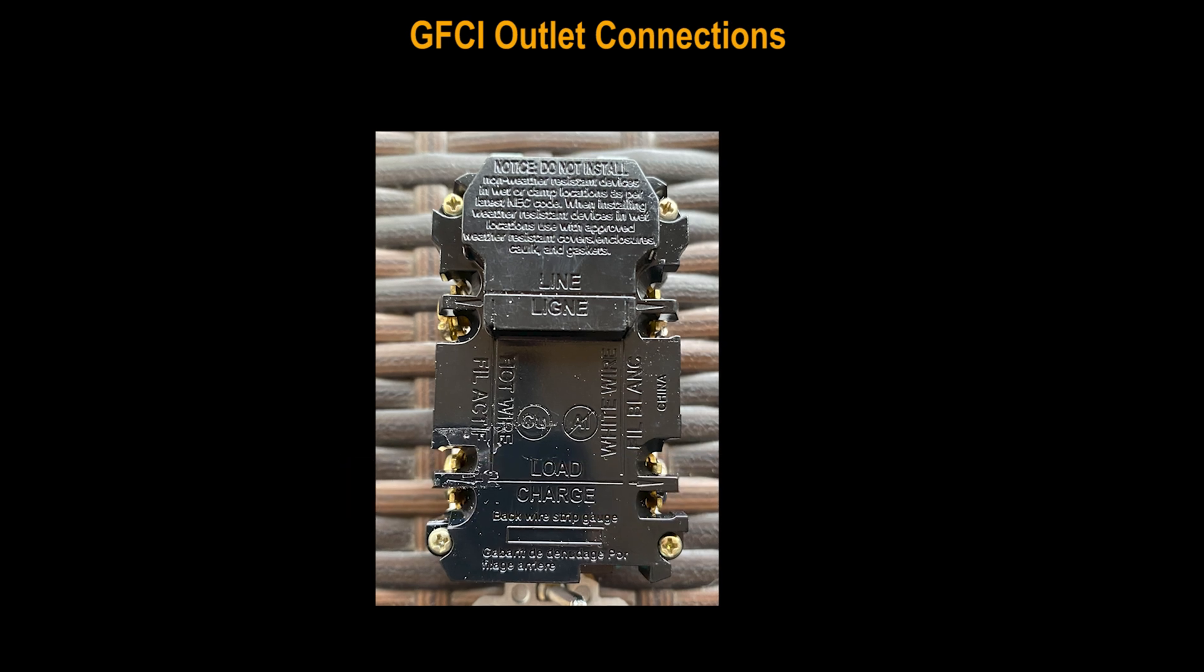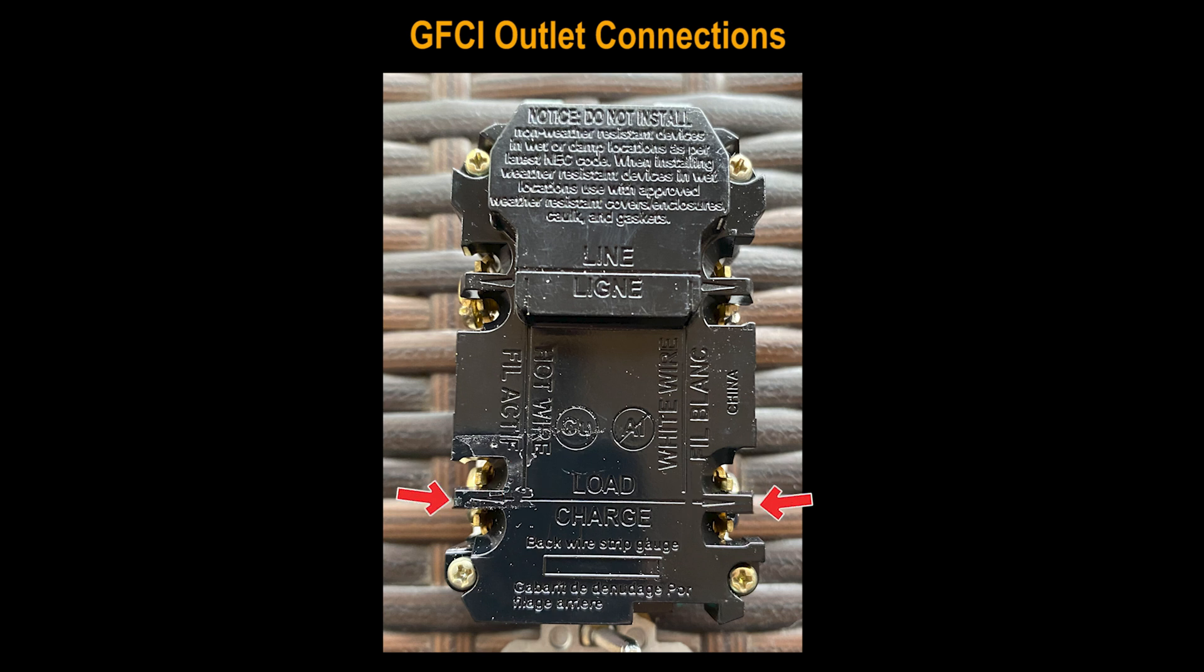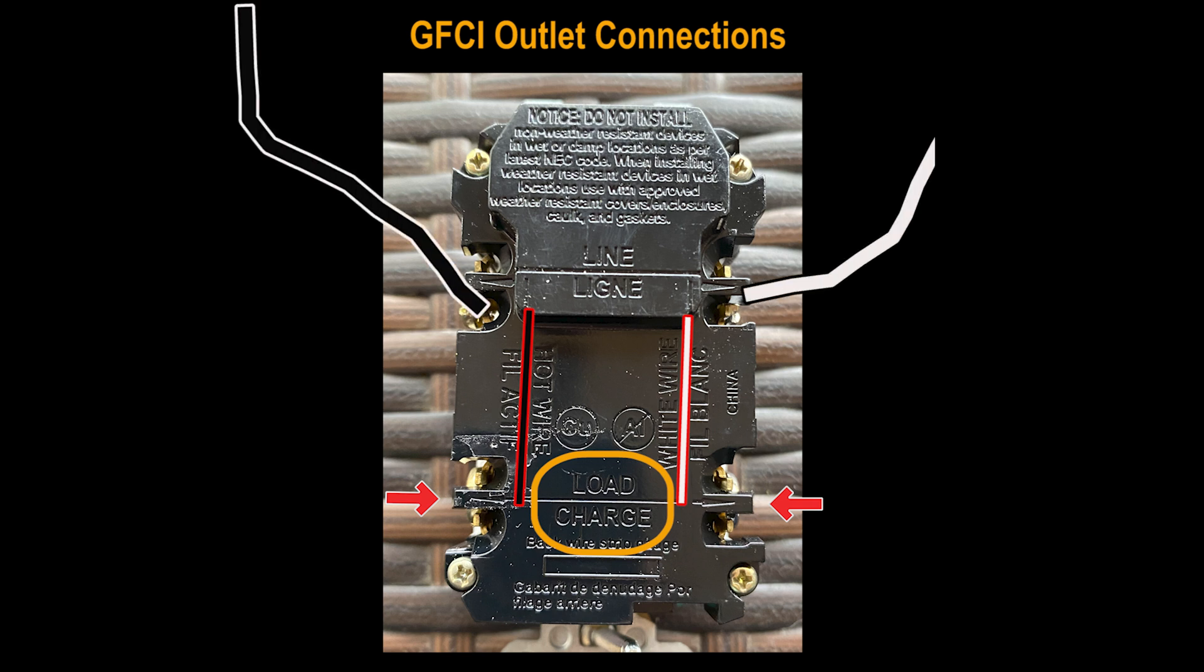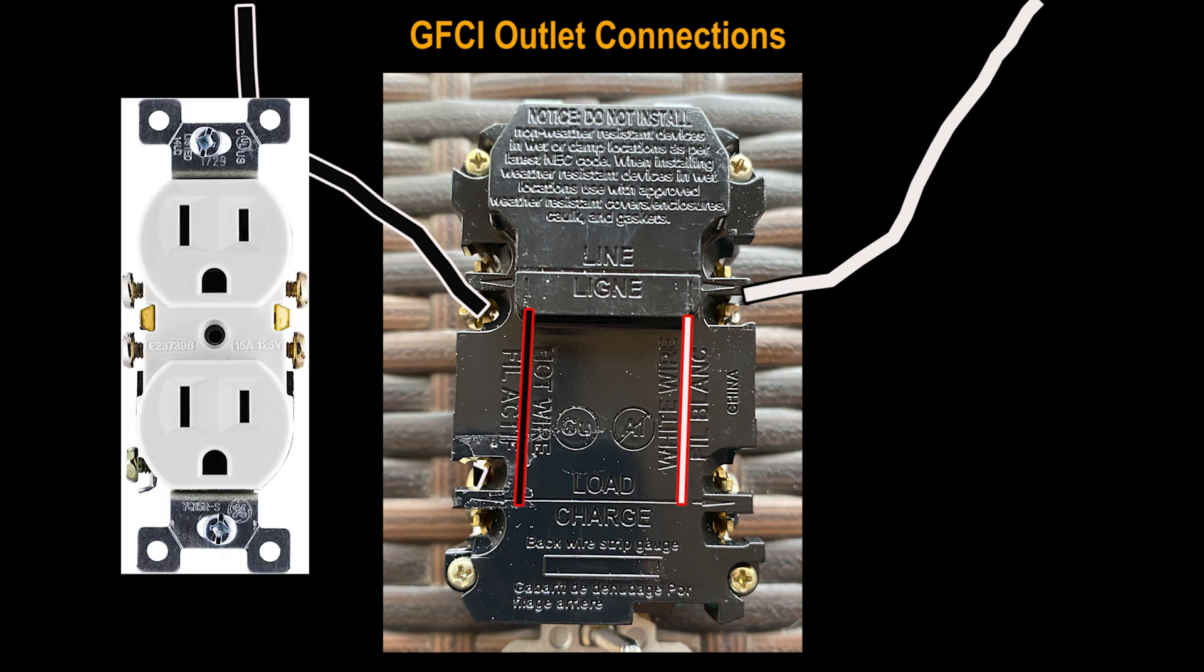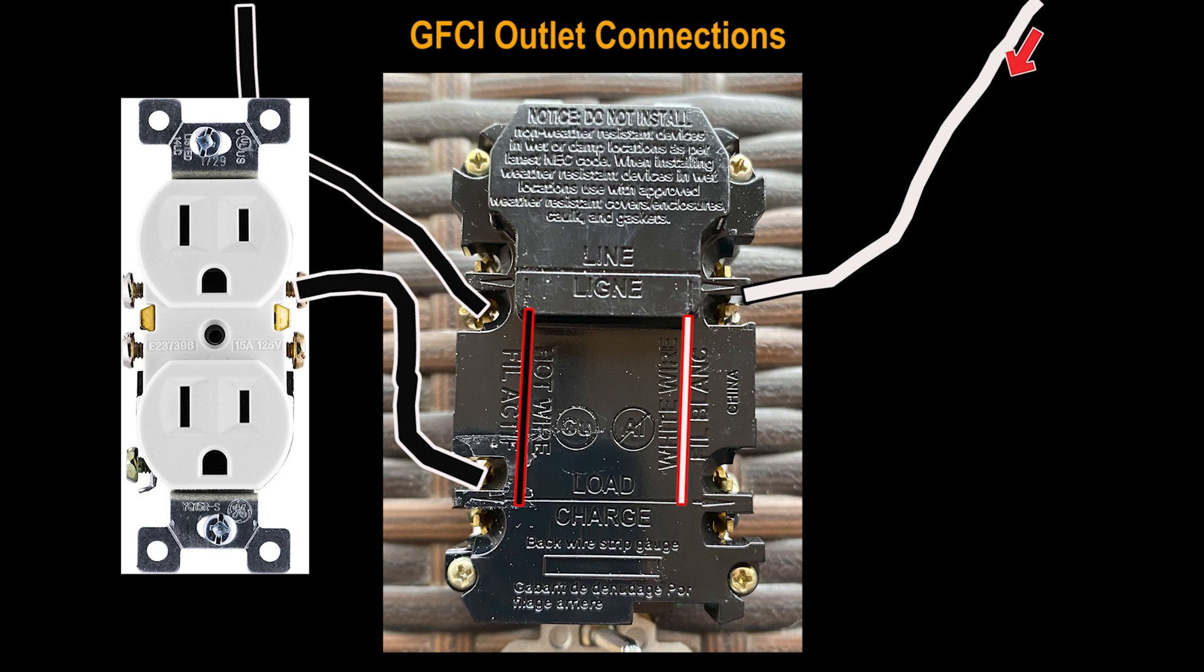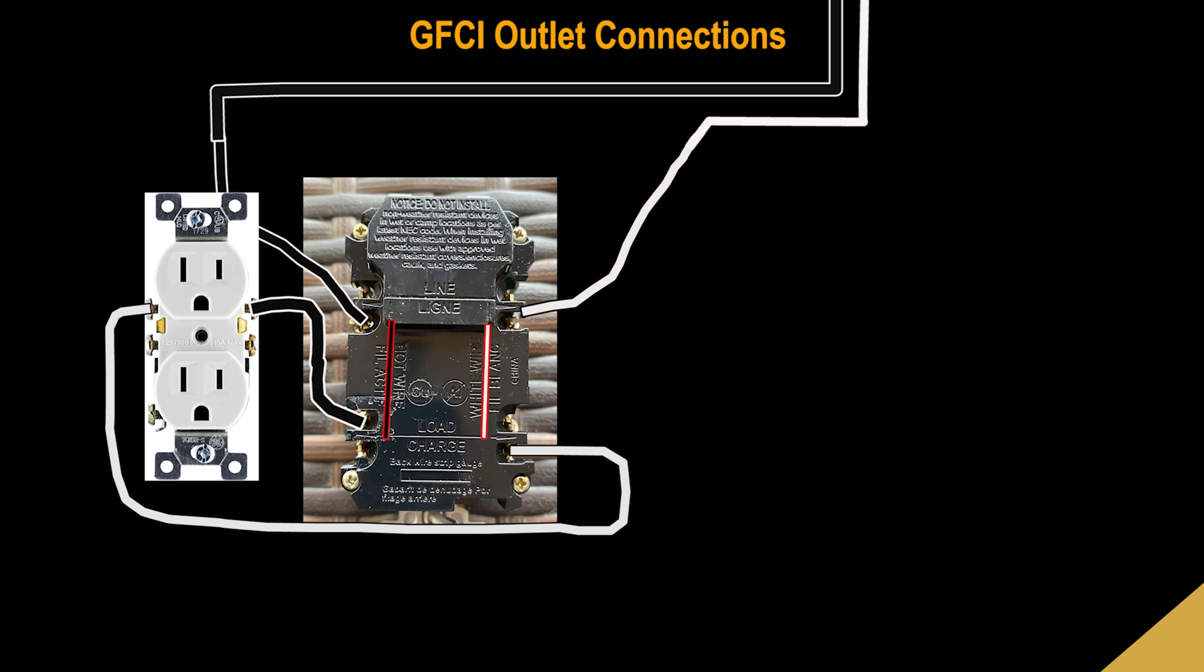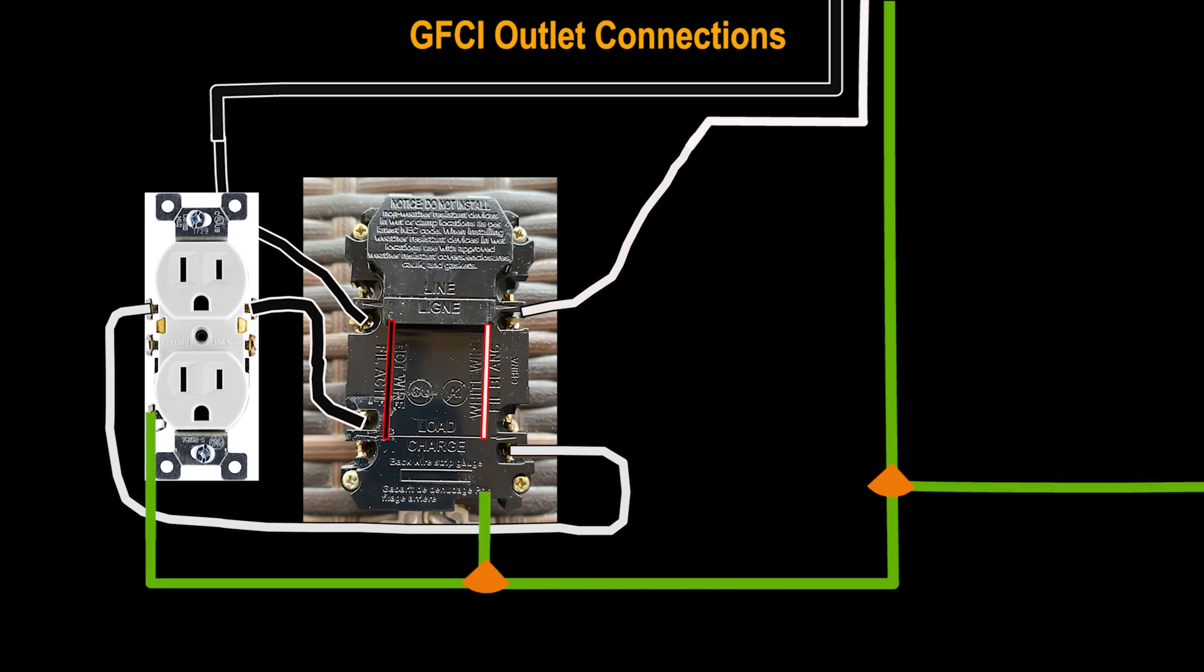Let's remove the protective sticker to reveal the additional connections on the outlet to see where these extra wires go and what purpose they serve. There is one additional connection on each side, located above or below the hot and neutral connections. This depends on a manufacturer. These two screws are directly connected to whatever is above or below it, similar to a light switch that is always on. This connection is always labeled as load or charge, since it charges the wire with the current to be transferred down to another outlet or a light switch by replicating the main connection. If it's on the side of hot, then this load screw sends the hot current forward. This means that on the other end of this wire, it must be connected into another outlet or a light switch in the hot slot. The same is for the neutral. The chain starts at the circuit breaker, going in into the outlet, then leaving the outlet through the bottom and connecting to the next outlet's neutral main connection. The ground connection might not be easily seen, but it follows the same route: goes from the breaker to the outlet, into an outlet, into an outlet, and so on.